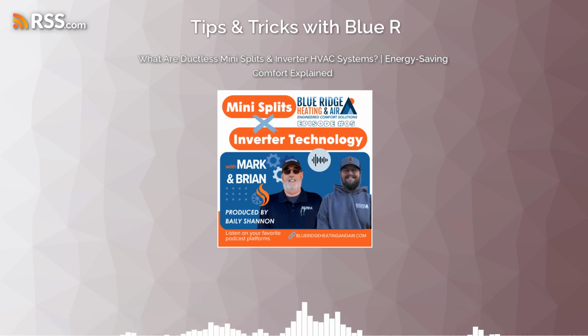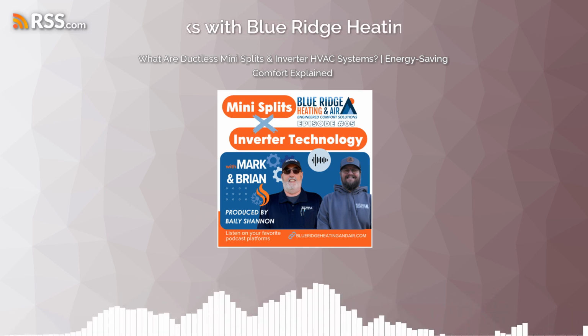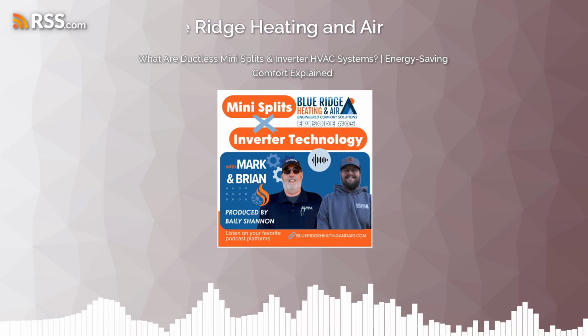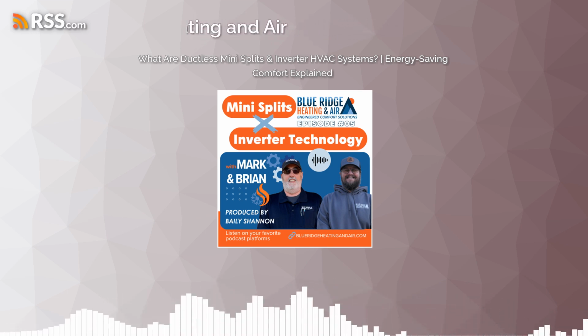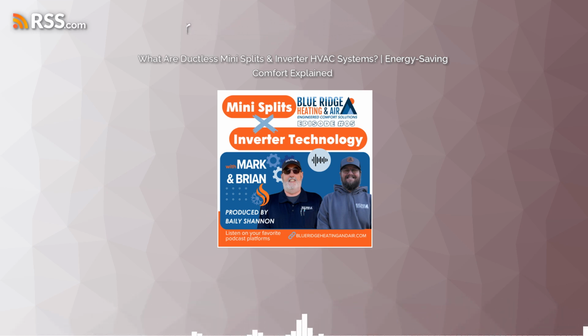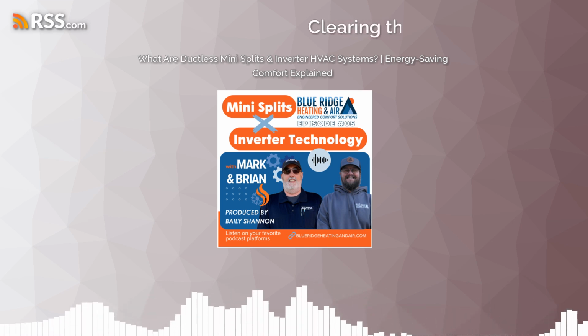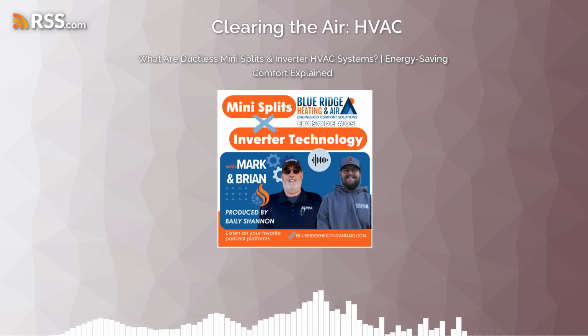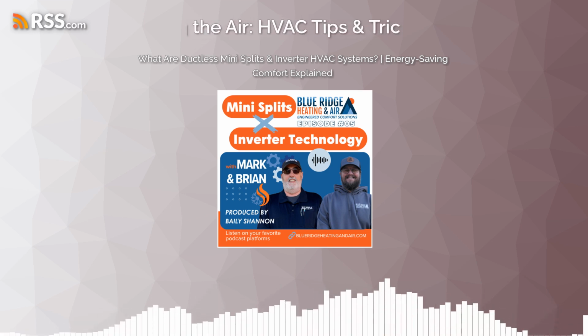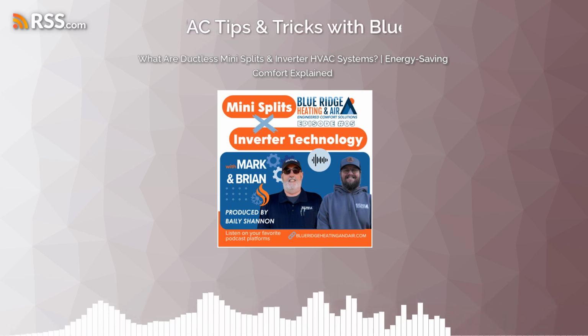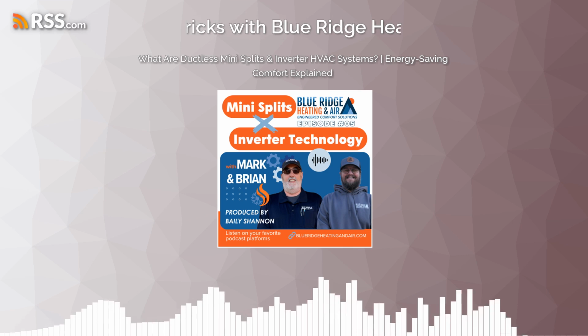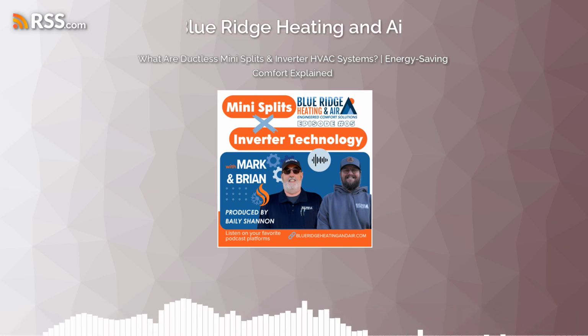But the inverter delivers 220 volts to the outside unit, then converts that voltage to DC, making the three-phase compressor able to ramp up or slow down based on the amount of voltage the inverter sends to the compressor.